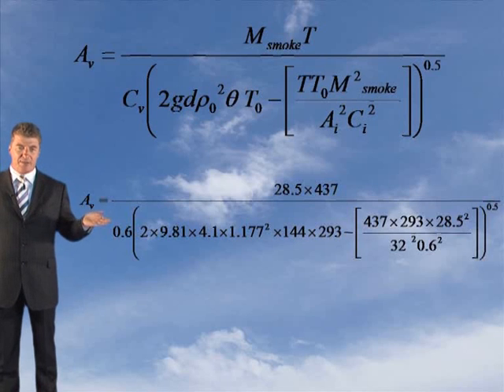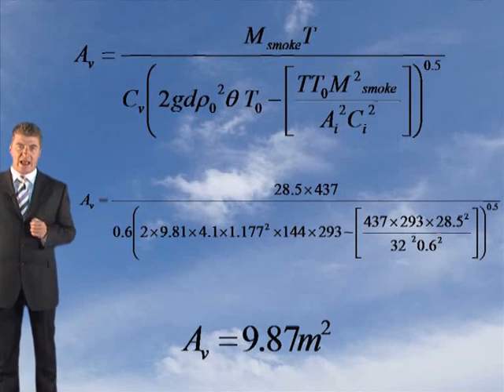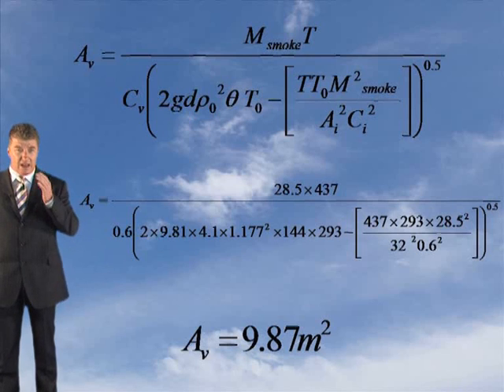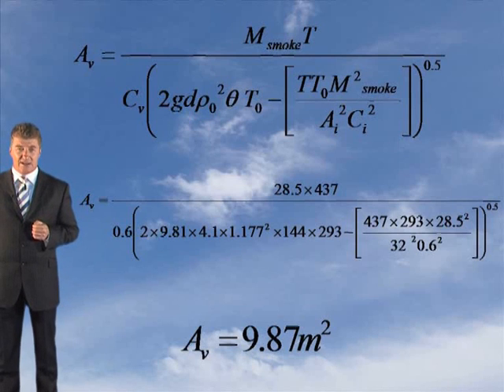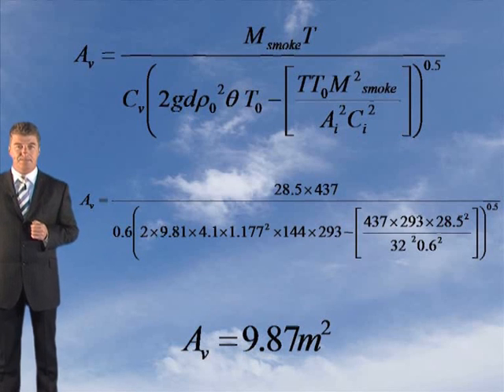When you put in your known variables, you should have got an AV requirement of 9.87 square meters. So you need 9.87 square meters of geometric area based on a coefficient of 0.6.